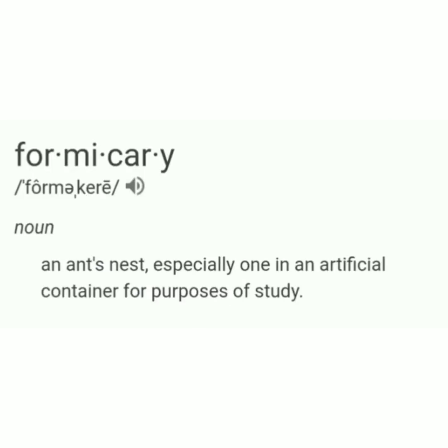Now that we've defined what formicary is, why have we chosen that term to describe leaks in copper piping in evaporator coils? Well, if you were to take an anthill and had a bunch of ants burrowing their way through it, then cut that hill in half and looked inside, you'd have all sorts of little tunnels. A piece of copper pipe with formicary corrosion looks very similar to that — that's where we get the term formicary corrosion.